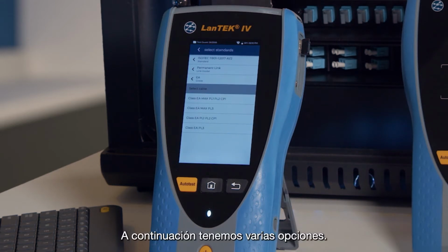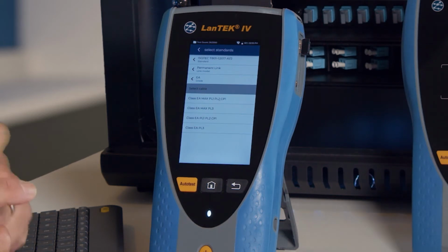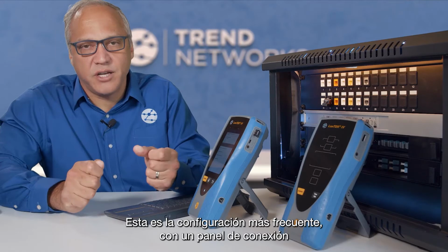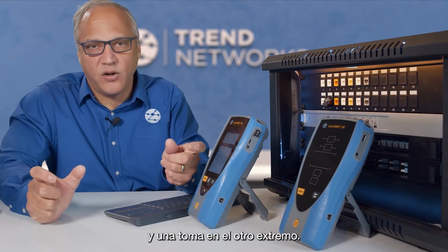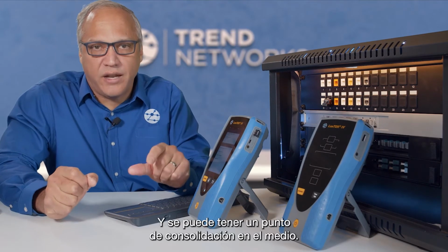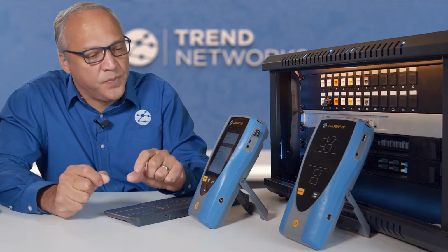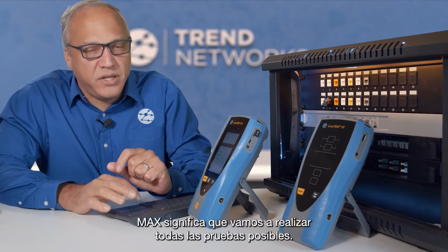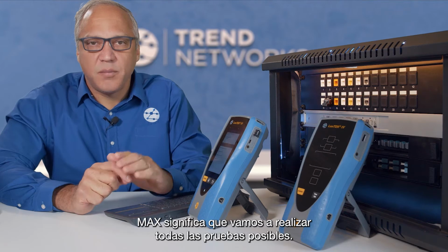Now, once we get down here, we have several choices. We have EA Max, PL1, PL2, CP1. So this is the most typical configuration where you're going to have a patch panel and an outlet at one end, and you can have a consolidation point in the middle. And Max means that we are going to run all of the possible tests.